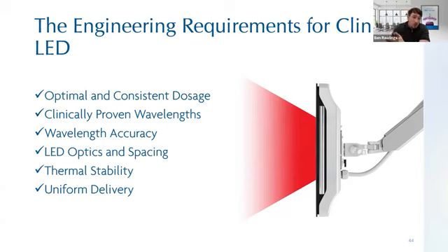And obviously with that, we're using the most clinically validated wavelengths, and we keep up to date with the literature on that. We're always trying to be state of the art. So anytime there's a change in the literature, we're reviewing that, seeing how that impacts our devices. At the moment, we know that we're using the most clinically validated wavelengths, and obviously, Dermalux sees the results off the back of that. And then you have the electrical and mechanical parameters of ensuring the spacing of the LEDs, ensuring they're thermally controlled, and then we've got a uniform delivery across the skin.